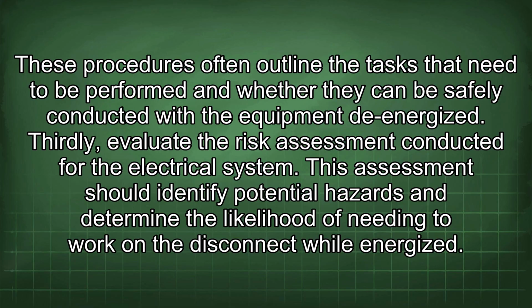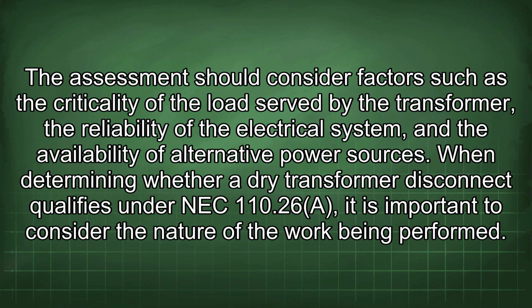equipment energized. Thirdly, evaluate the risk assessment conducted for the electrical system. This assessment should identify potential hazards and determine the likelihood of needing to work on the disconnect while energized. The assessment should consider factors such as the criticality of the load served by the transformer, the reliability of the electrical system, and the availability of alternative power sources.